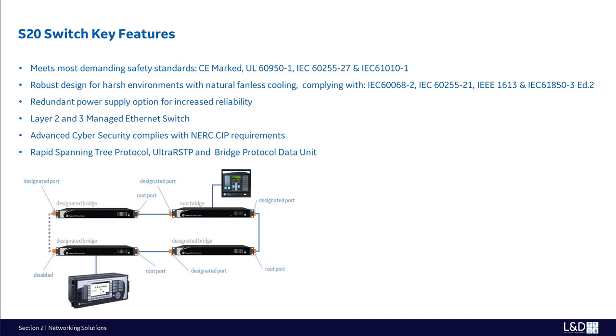In addition, the IEC 61850-90-4 technical report specifies the Rapid Spanning Tree Protocol, RSTP, when looped topologies, such as the ring topology, are required at the station level of substation networks.